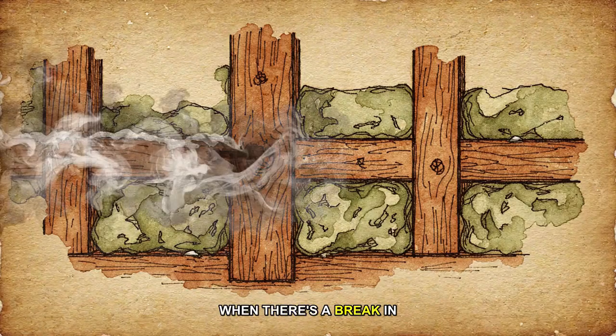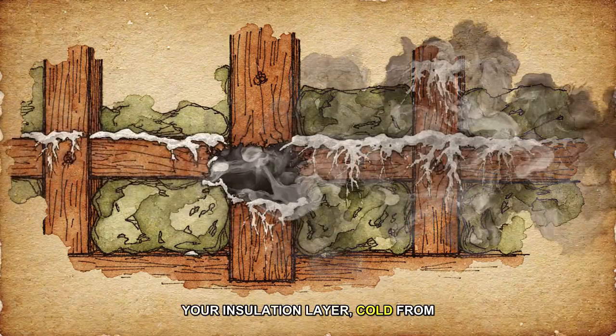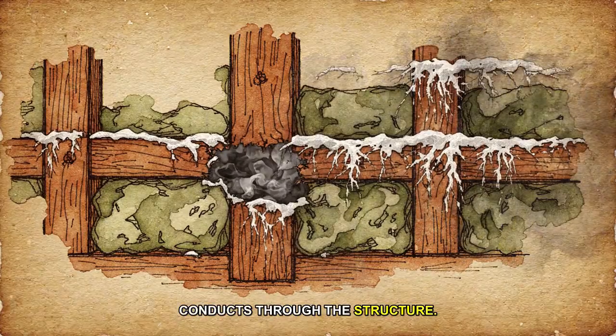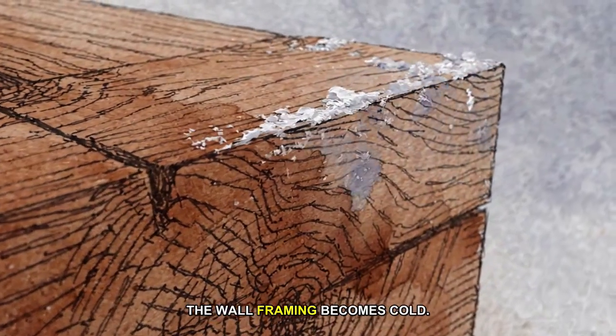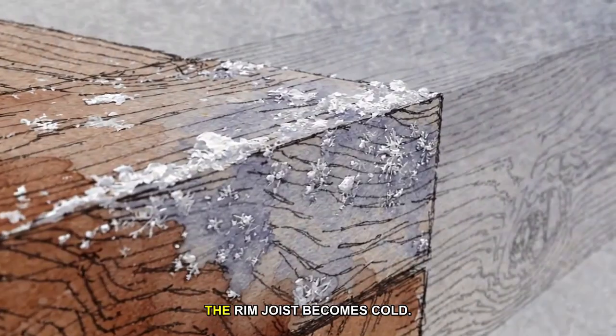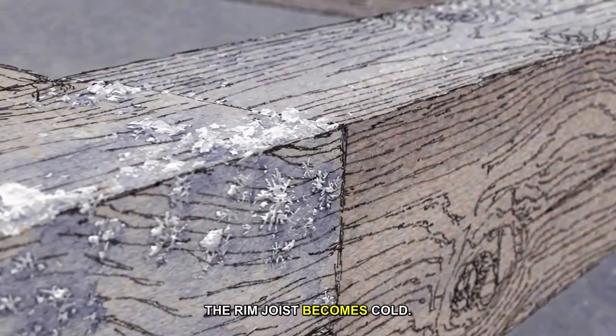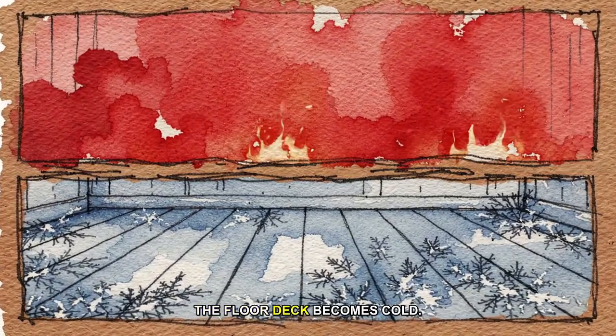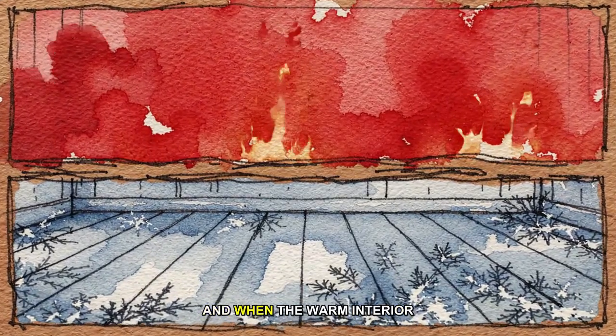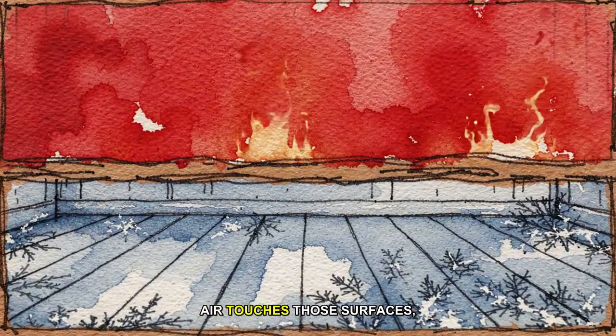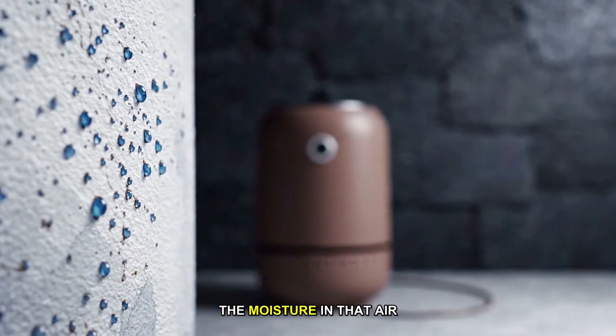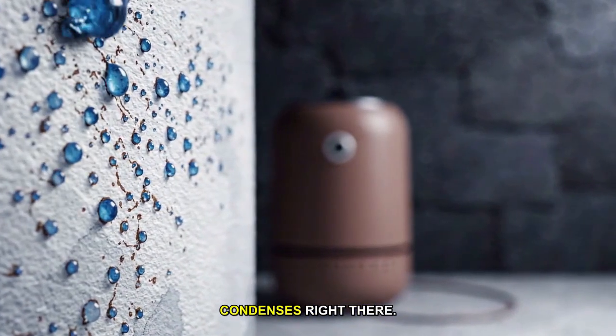When there's a break in your insulation layer, cold from outside conducts through the structure. The wall framing becomes cold. The rim joist becomes cold. The floor deck becomes cold. And when the warm interior air touches those surfaces, the moisture in that air condenses right there.